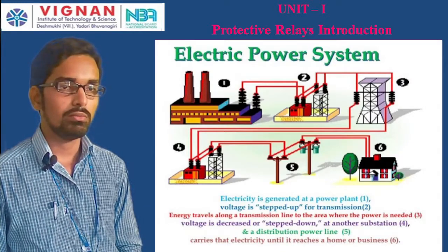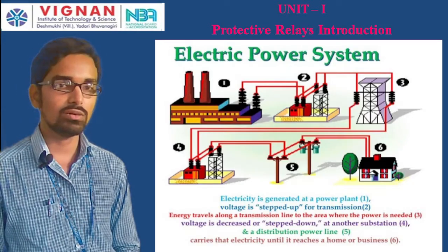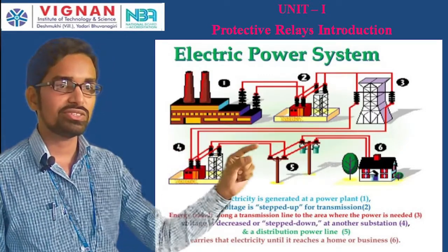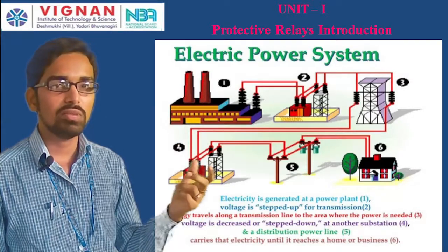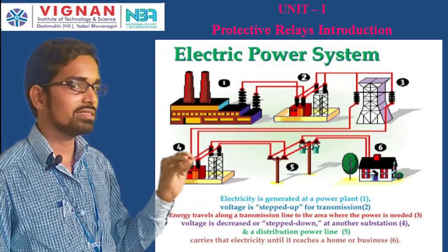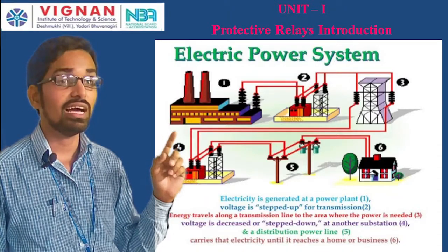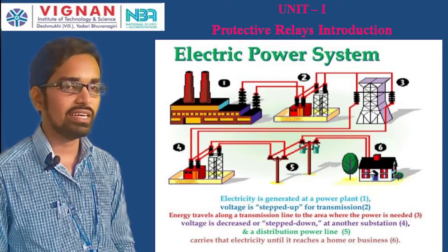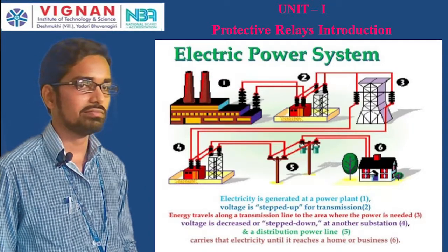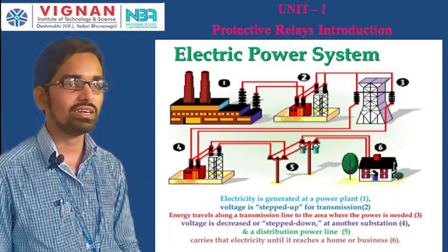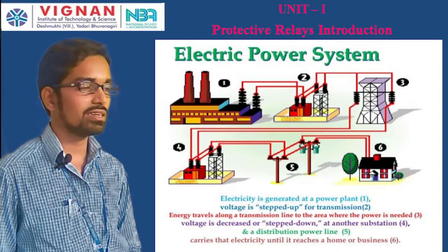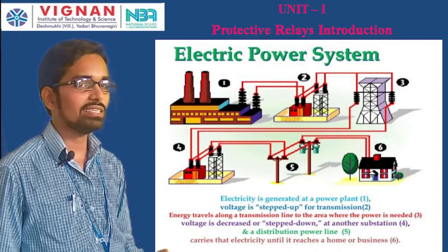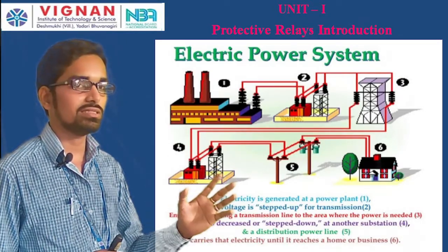The protection system costs only about 5% of the total equipment cost. For example, a generator may cost crores of rupees; by investing just 5% of that cost we can protect it. At the generator the most severe fault is an LG (line-to-ground) fault, whereas in the transmission system the most severe fault is a symmetrical three-phase fault.